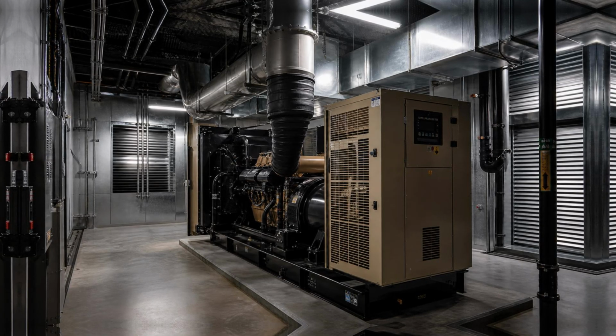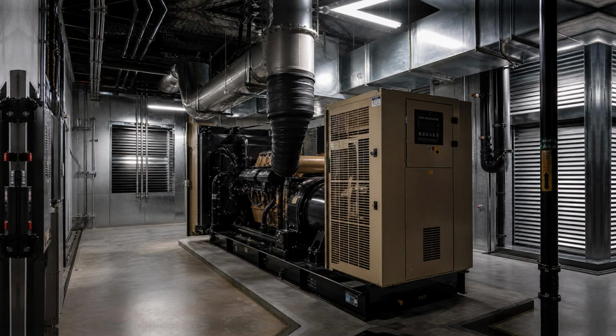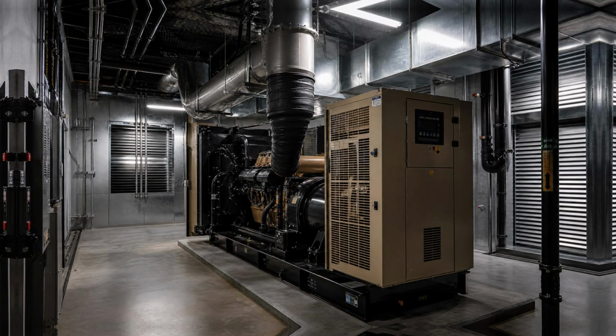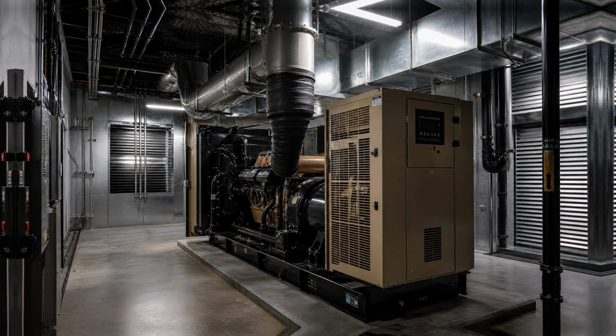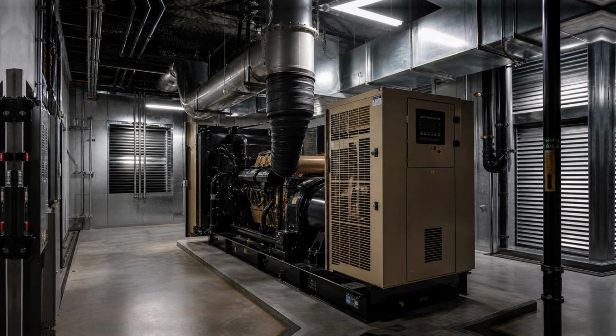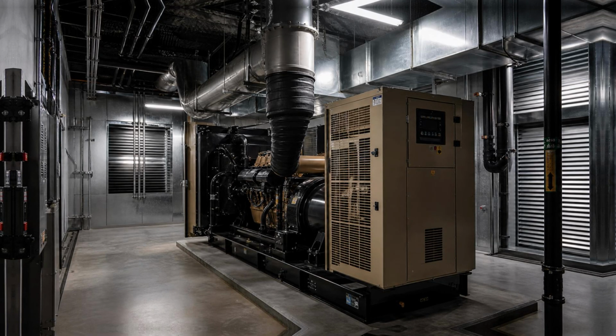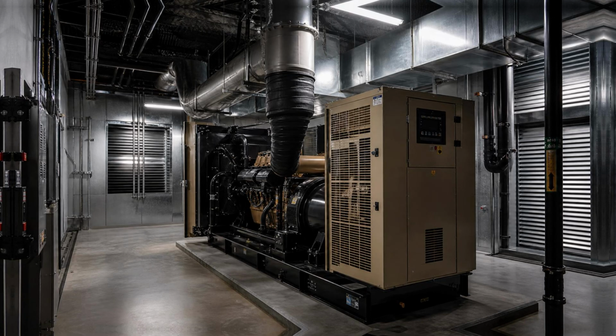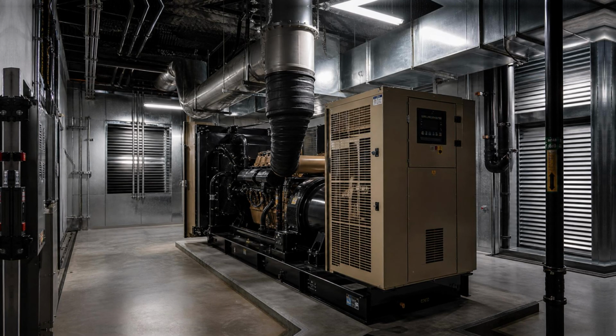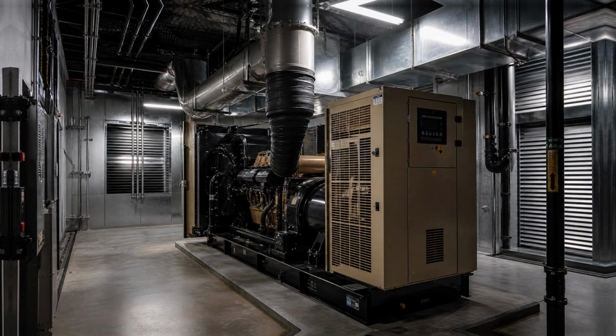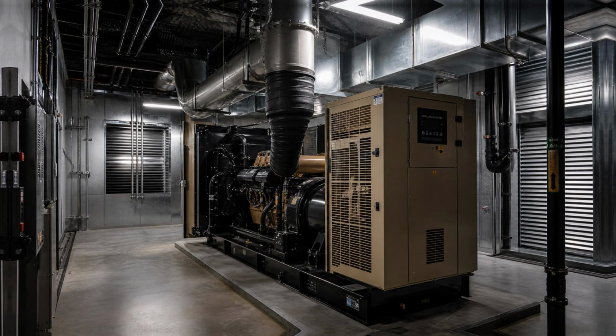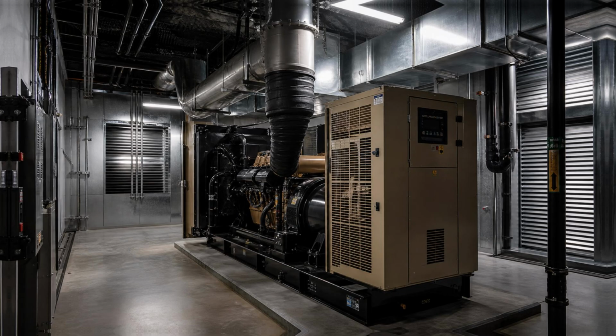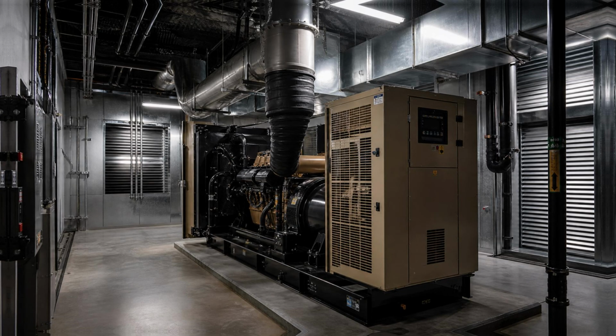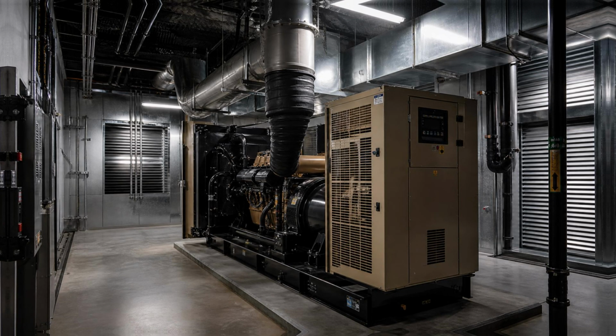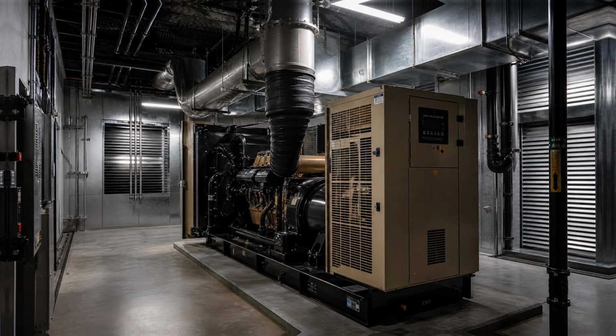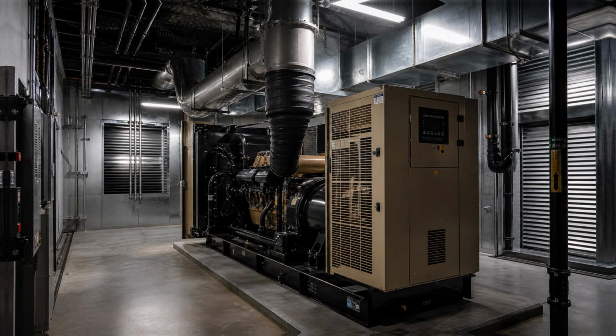And so the health of the batteries is checked, not constantly, not dramatically, but on a schedule, measured, recorded, compared against baseline values, impedance tests, load bank tests, runtime verifications, all of it quiet work, carried out in the background, producing numbers that sit in maintenance logs and inform replacement schedules and ensure that the stored energy the system depends upon is genuinely there when it is needed. This is one of the less visible rhythms of emergency power maintenance.